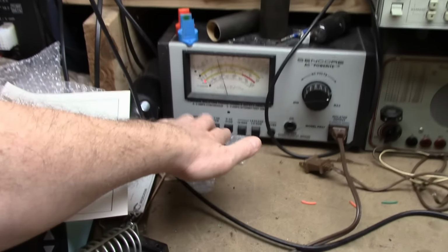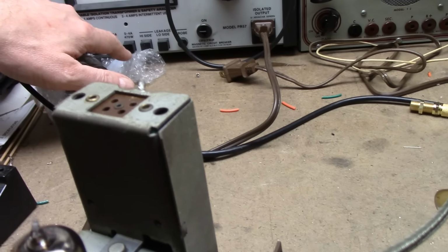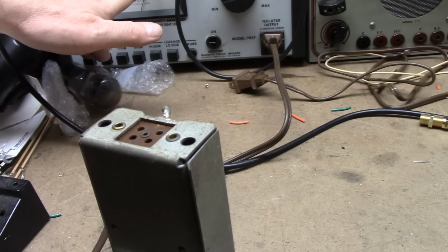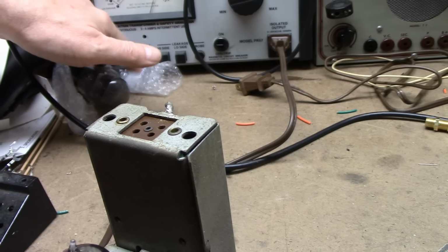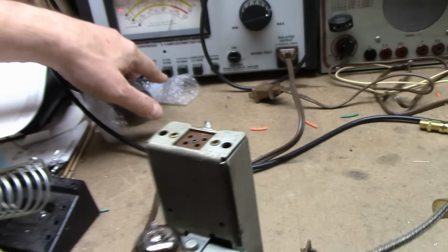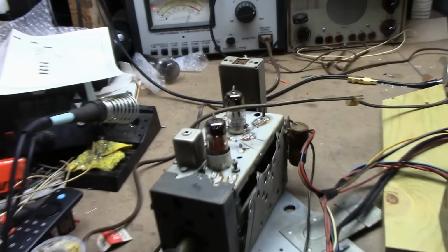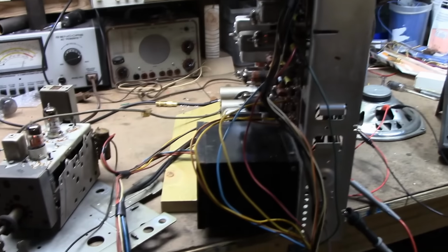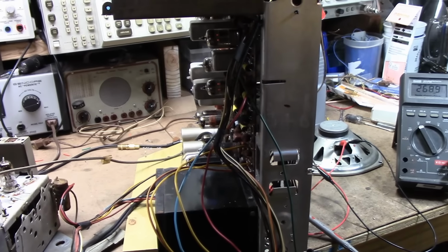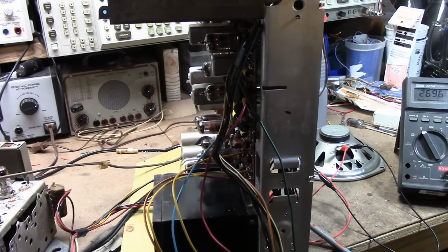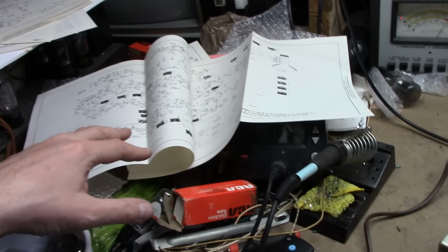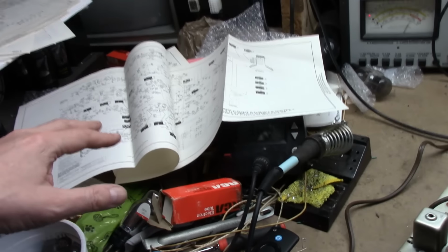So let's check to see what we're actually feeding in. I know this is slightly off from testing the output - it says 117, probably more like 115 or 114. Should be a lot closer to 390, I would think, but I'm not going to get too hung up on that. I take these SAM voltage readings with a bit of a grain of salt - if I'm plus or minus 20%, we're okay.